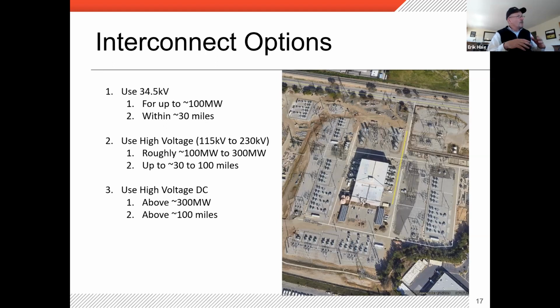To get up to roughly 300 megawatts, or maybe 400 to 500 megawatts, you can use high voltage AC at 115 kV to 230 kV, and that will take you on the order of 50 to 100 miles. But as you go to longer lengths, you'll have technical challenges due to the capacitance of the cable. Anything above that, you're going to have to use high voltage DC.